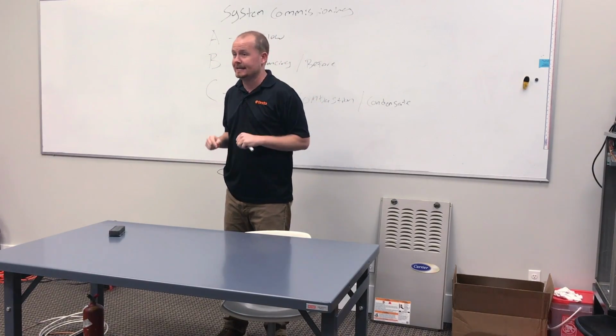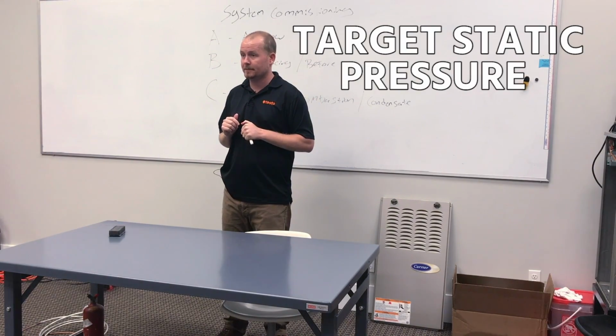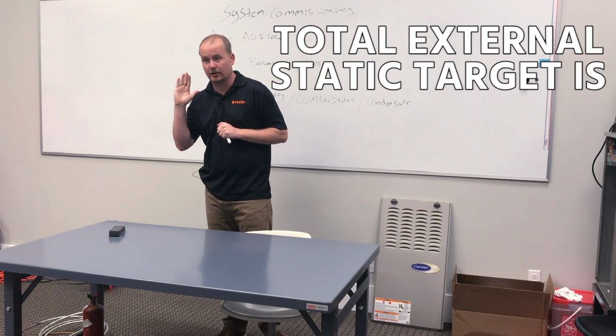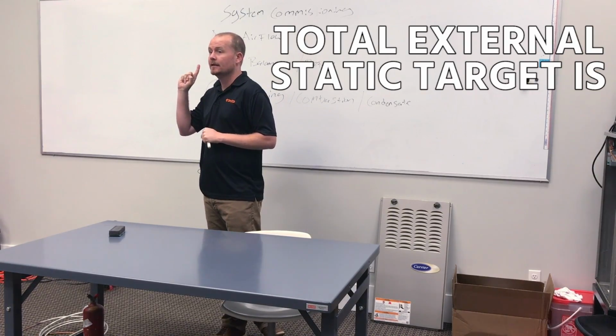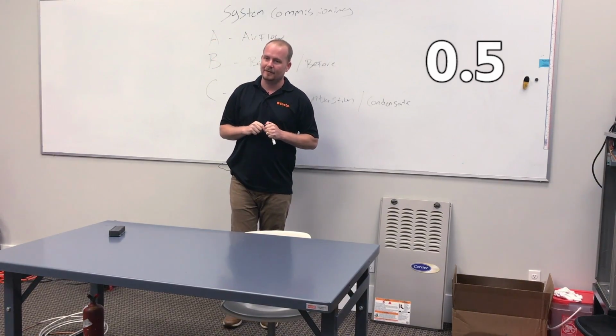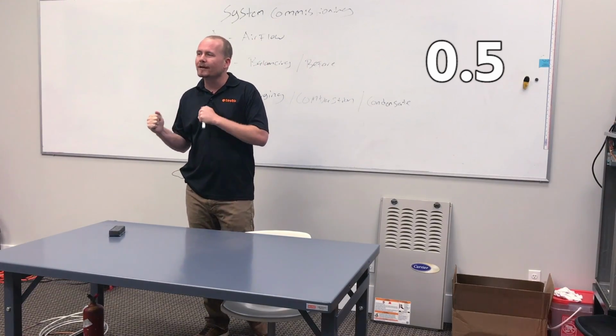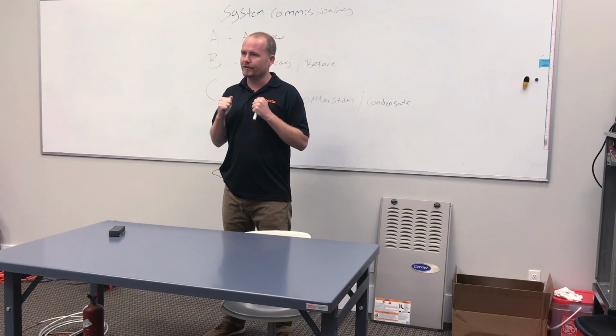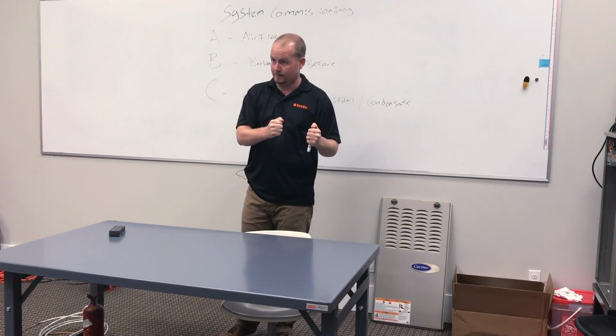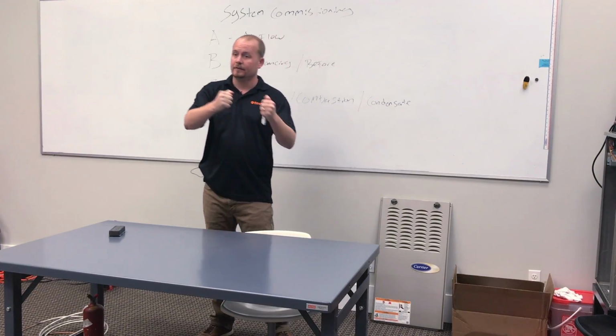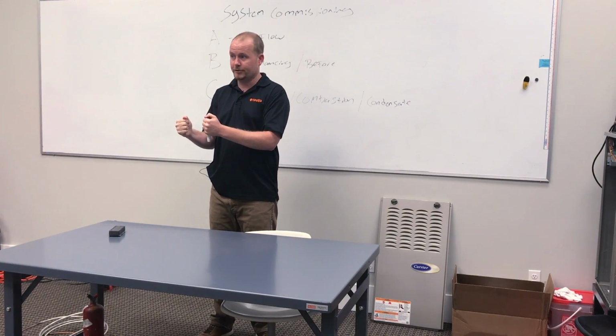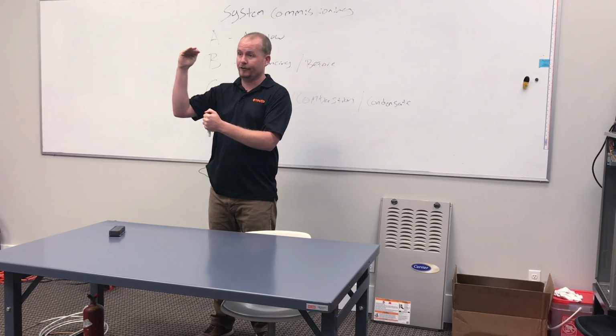It says right on the data tag what your target static pressure is, which, what is it? Total external static target for the units we install is 0.5. Man, we've made progress. So you don't really have to do a lot of thinking. All you've got to do is set it up right, then hit that 0.5 target as close as you can. And know that for every bit that you go over that 0.5, you're taking a hit.